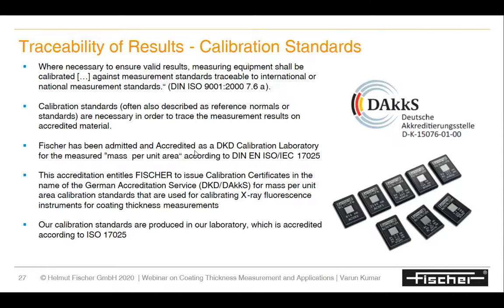For traceability of results and calibration standards, Fischer has a certified laboratory in Germany with standards for almost all types of coatings. Customers can specify their application and receive a certified sample. Fischer is accredited by DKD calibration laboratories for mass per unit area measurements per DIN EN ISO/IEC 17025. All calibration processes follow ISO 17025.